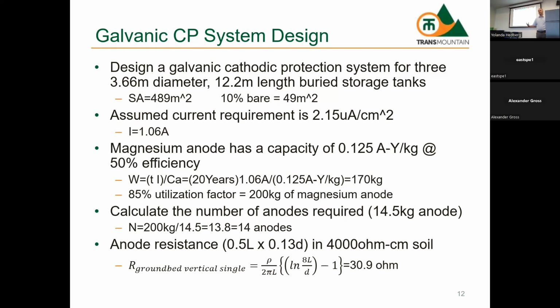The more aerated the soil is, the type of grains that are in the soil, the moisture content of the soil, it all influences your soil resistivity. And the higher that gets, you can't use galvanic.